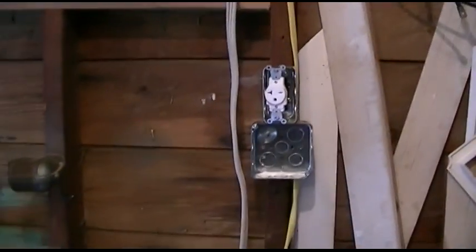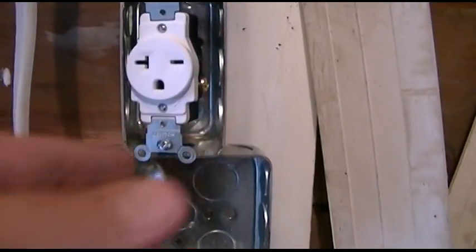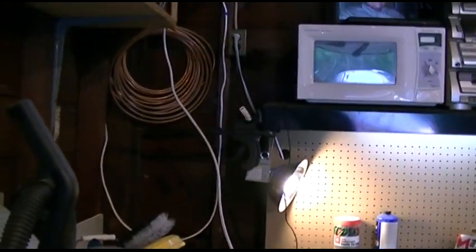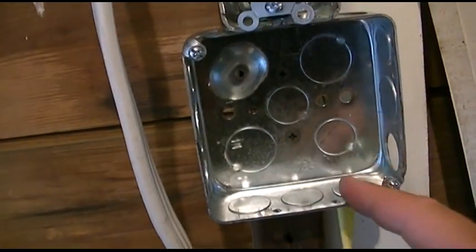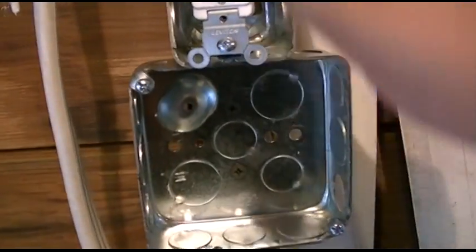Not thinking everything through as usual — this wire is just hanging right there. That's where the AC outlet is going to go. There's going to be four outlets in this box here, each on a 15 amp. We're going to run out from over here along the wall over to the corner next to the bench. Power's coming down there, going in to here — one branch on one outlet, the other branch on the other. That's going to come off on a 14-2, head through there, and along the beam across the way to the outlet. So this guy can have his own branch also.